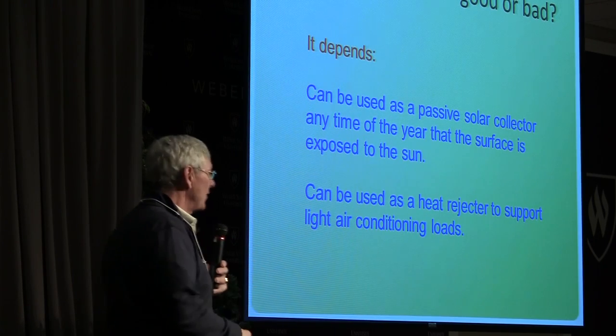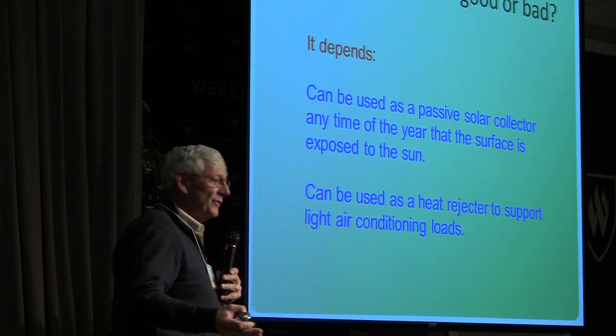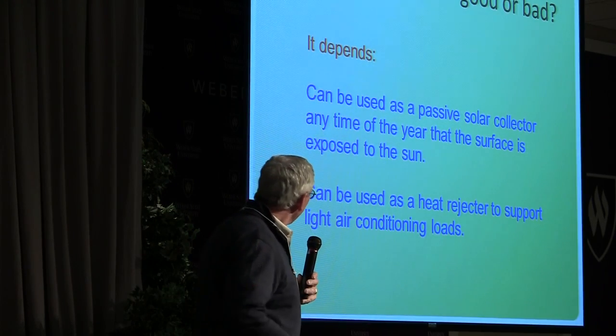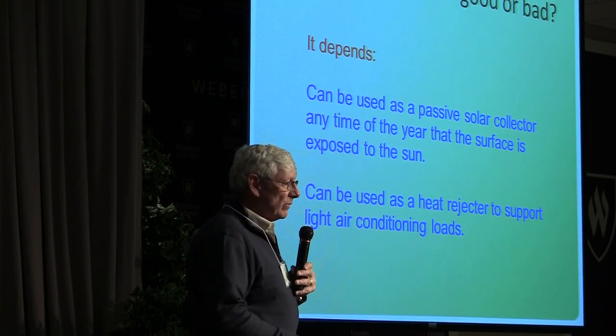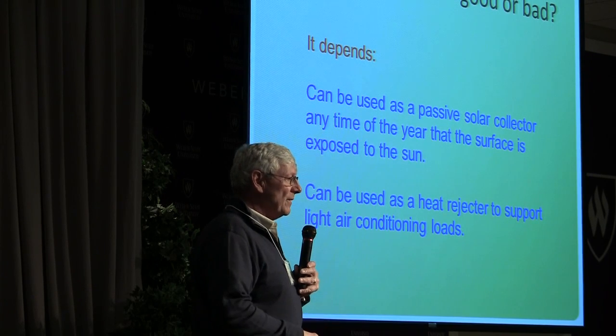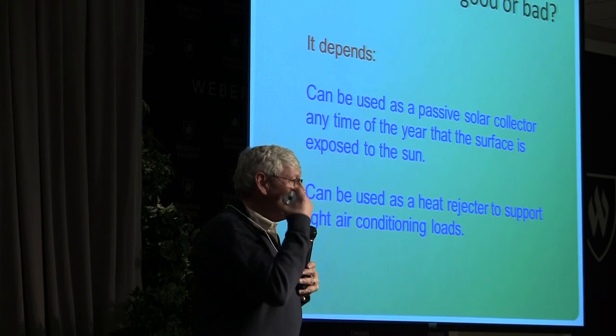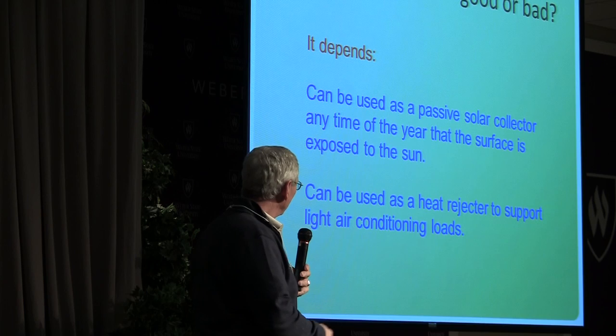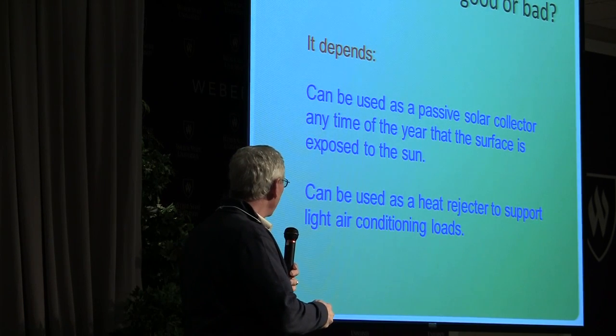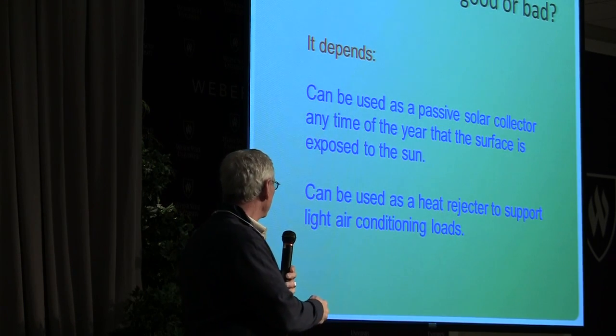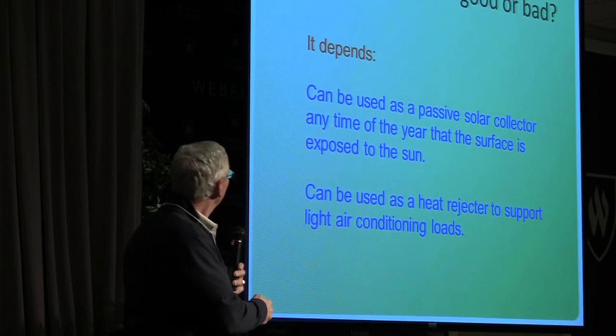You're talking about 125 BTUs per square foot to melt snow. In our area, it takes a lot less, 15 to 20, to do the same thing in the home. So it's one of those things we have to deal with, but it's also a health and safety issue in schools, loading docks, and things like that.